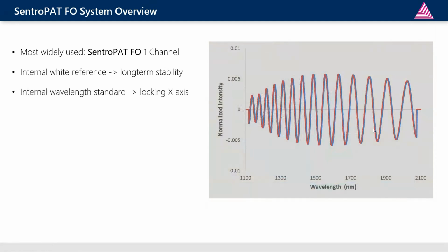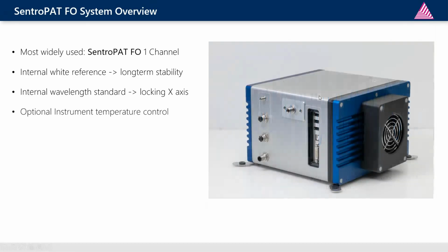Inside the SentroPAT FO, we have an internal wavelength standard, like a Fabry-Perot type filter. And whenever you see a wavelength shift happening, the spectrometer will be corrected back to its correct original wavelength axis. So it's actually locking the x-axis. There are versions of the instrument which are temperature controlled. So that means the whole instrument itself can be temperature controlled, including the box. This version you see here now is a version with a 9 watt internal light source, which is used for the MS7 probes.